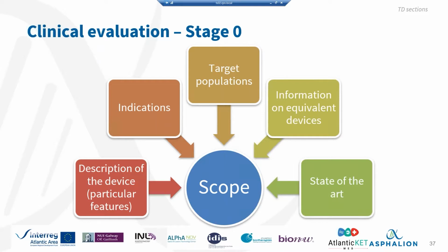Okay. Also, another fundamental point is the indications for what the device is going to be used. This is something that has to be totally defined. Obviously, you've got to take into account, once you're doing your clinical evaluation, what your device is being used for. It's not the same. For instance, before we had this question regarding the software as a class 1 or as class 2A.